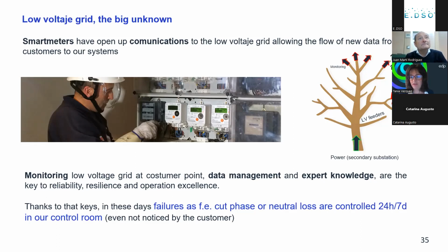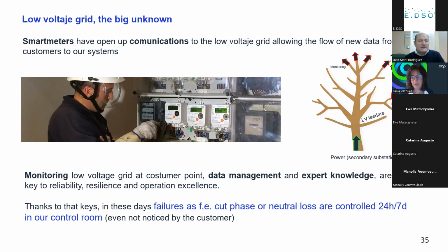With the smart meter, for the first time, we are able to monitor the energy that flows to the last point of the grid, the customers. If we use that data in a smart way, we are not only able to do meter readings, we are able to detect failures, such as cut phase or neutral loss, through alarms from the smart meters. So smart meters were the first step to observability in low voltage grids.